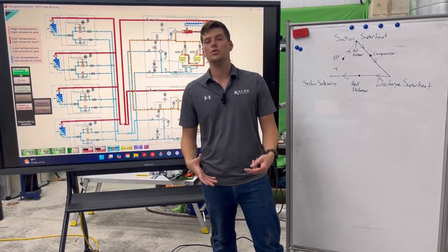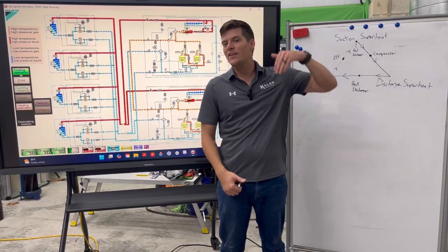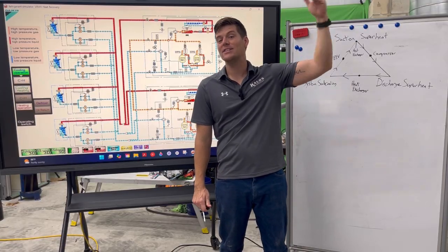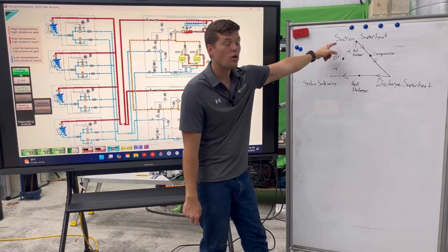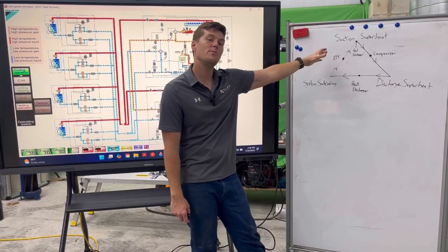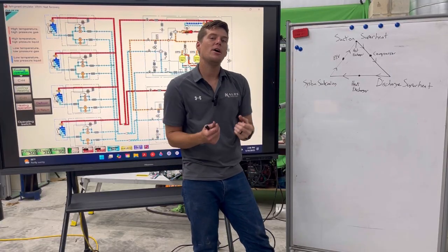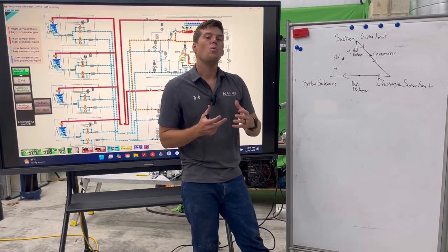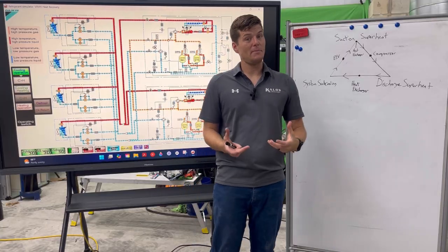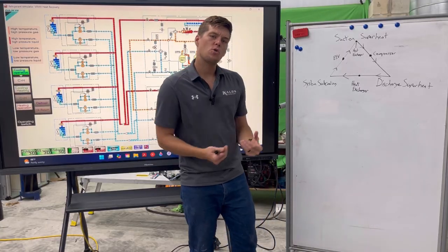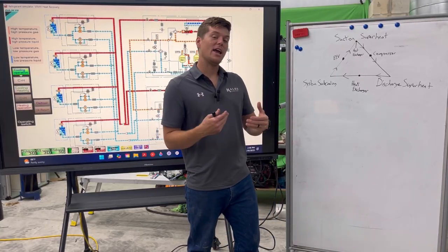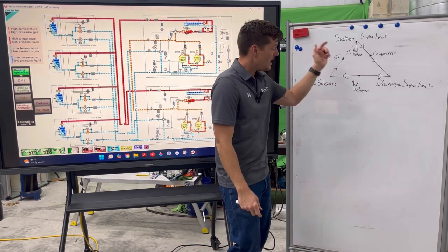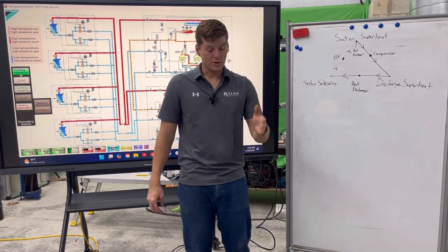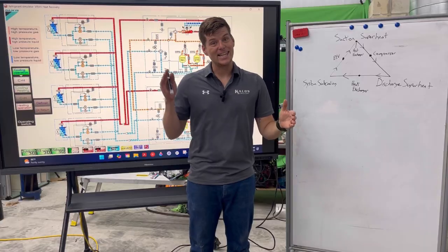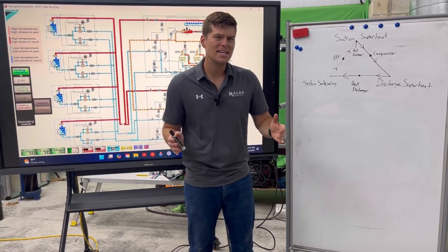That's how we get to discharge superheat. Elevated discharge superheat tells me that it doesn't get enough vapor, which is, again, why we start with suction superheat. We start with suction superheat because it's telling us how much vapor I am getting back to my compressor. What is the quality of vapor getting back to my compressor? Because once I know what the quality is coming into my compressor, then I can measure my discharge superheat in the next corner and determine, between entering my compressor and leaving my compressor, how healthy is my compressor?